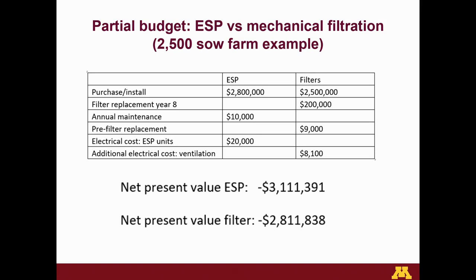Filter replacement you have in the filter system, and you don't in the ESP. Some maintenance, I put a number in. The pre-filter replacement on the filters. There's an additional electrical cost to run the ESPs, and I'm using some assumptions based on what they gave me for milliamps. We know the voltage at 11 kilovolts. The reduction in fan power because of the reduction in static pressure, or pressure drop, I plugged in using data from BESS Labs from the University of Illinois.